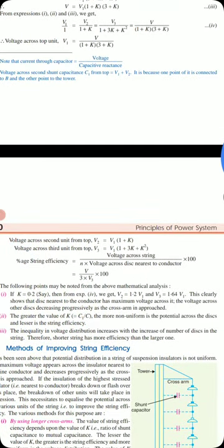From the total voltage expression, we can find V1 = V / [(1 + k)(3 + k)]. Then V2 = V1(1 + k), and V3 = V1(1 + 3k + k²). The string efficiency is given by V / (3 × V3), i.e., the total voltage divided by the number of disks multiplied by the voltage across the disk nearest to the conductor.